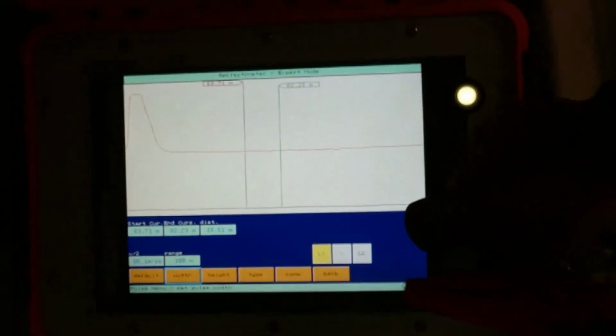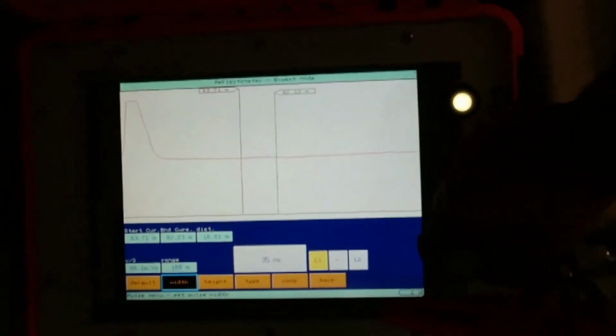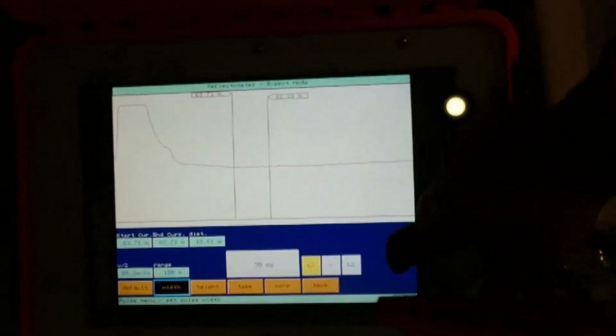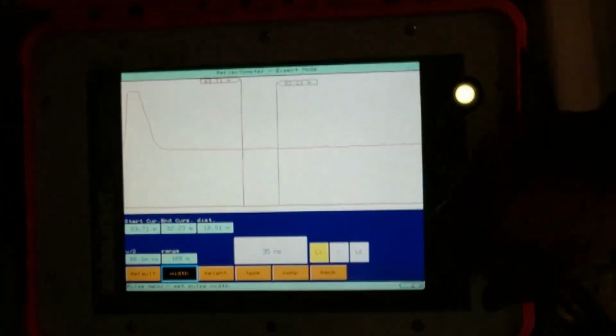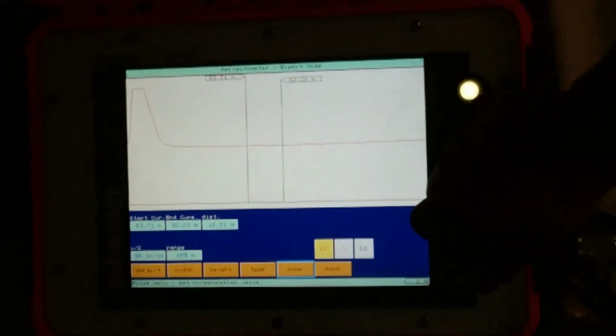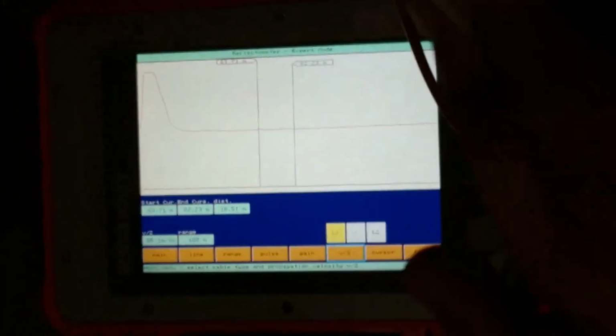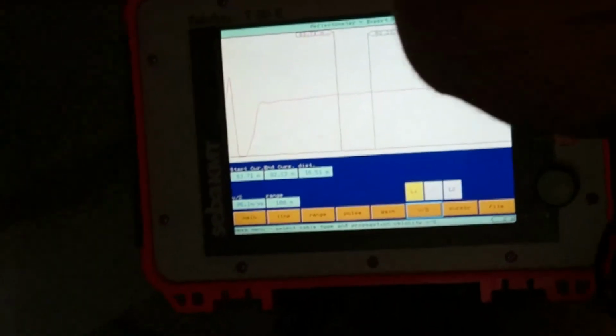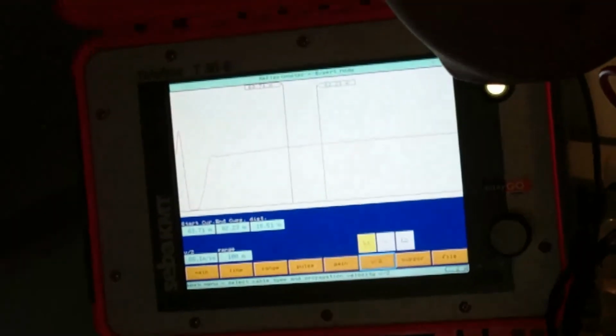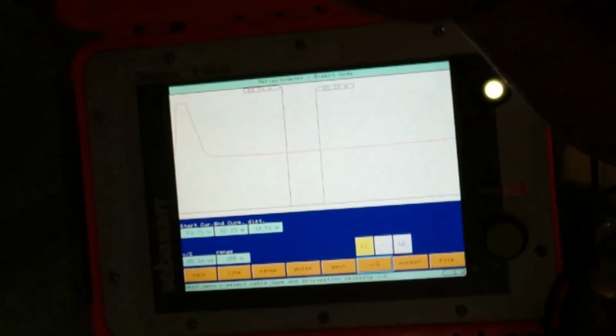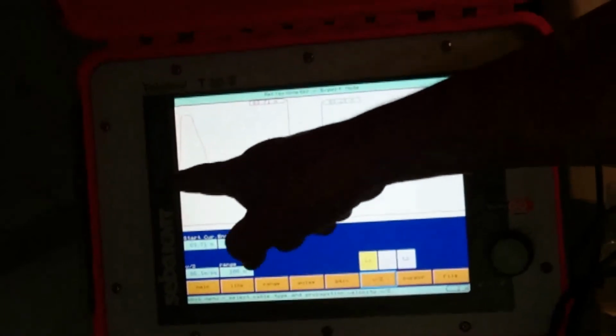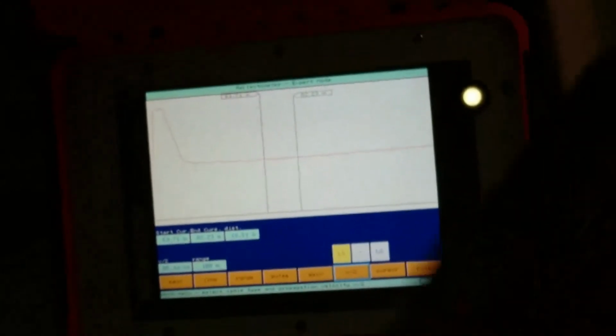I'll change the pulse width. This is for a longer cable. For a shorter cable we normally use 35 nanoseconds. We don't have cable here, we're using only the connector. If you have zero resistance, you'll get a very sharp negative trace. If you have a little ohm on it, say 50 ohm, then the short will not be very sharp, it will be visible somewhere, going negative but not very sharp - high peak, but short.